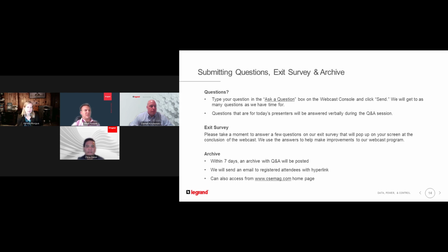Yeah, absolutely. And I'll have Chris chime in as well, if you feel the need to, Chris. But the answer is yes. You could use the fiber optic cable that comes with it. It comes in 2 different options. So we understand that a lot of data centers have a high security risk with any Wi-Fi or Bluetooth. So we did create them in both ways. Some industrial facilities, they don't mind having the Bluetooth and it's preferred. But there's larger data centers who are looking at security risks. They would look at the fiber optic type cable, which Chris had mentioned, you can get about 30 feet out with that. I think it's a 10-meter cable that's on there.